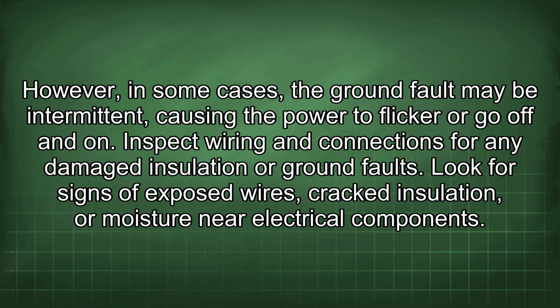However, in some cases the ground fault may be intermittent, causing the power to flicker or go off and on. Inspect wiring and connections for any damaged insulation or ground faults. Look for signs of exposed wires, cracked insulation, or moisture near electrical components.